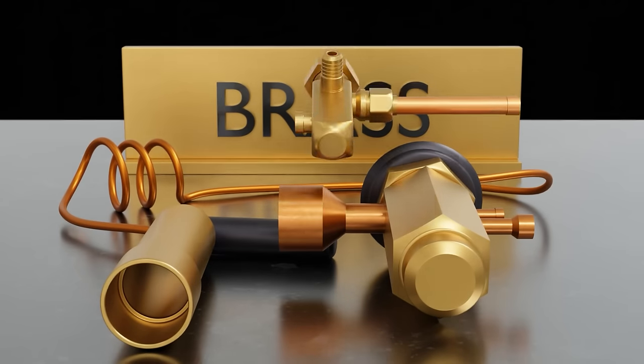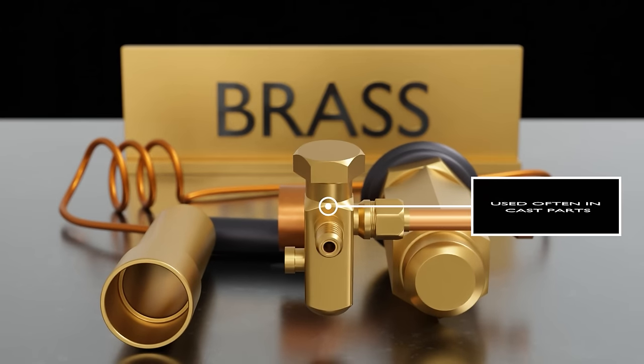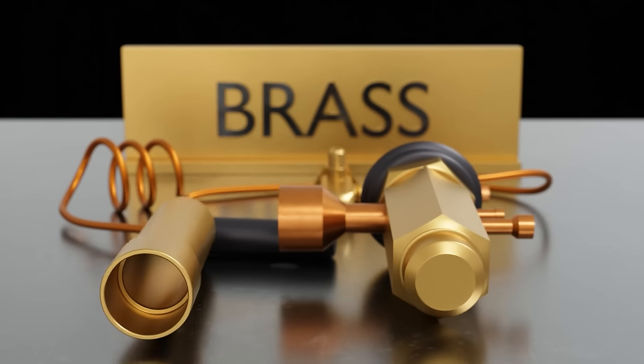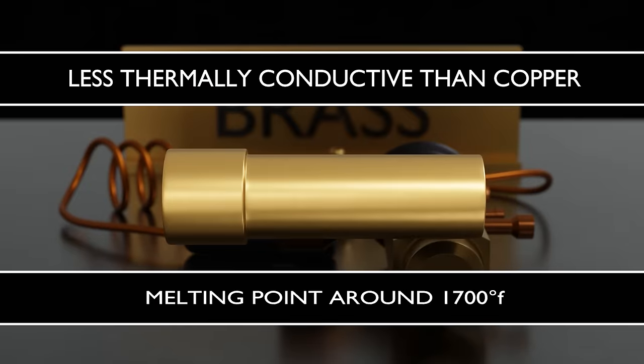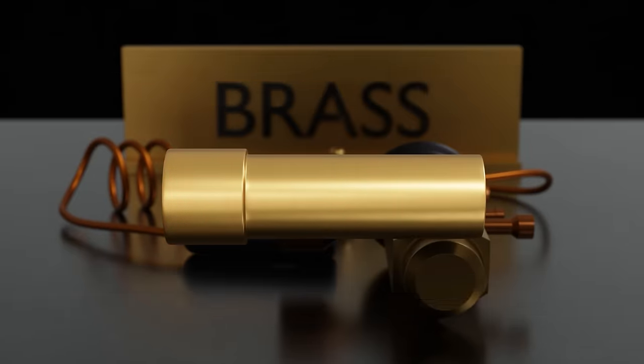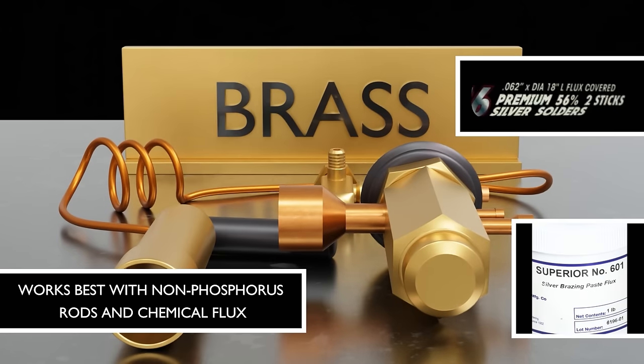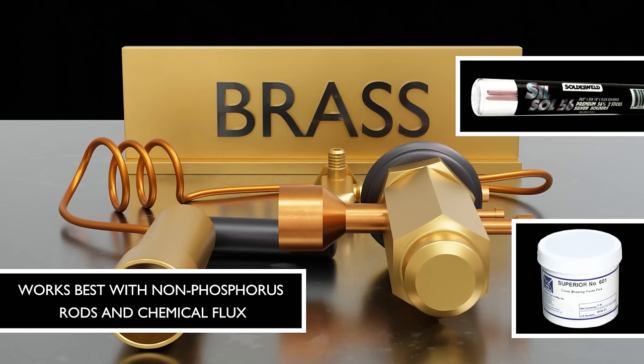Brass is a softer metal, and it's copper plus zinc, usually used in cast parts like valves. It's less thermally conductive than copper and has a lower melting temperature. When working with brass, it's best to work with non-phosphorus rods, like a 45% or 56% flux-coated, and work with a separate flux. You would generally be using a paste flux.